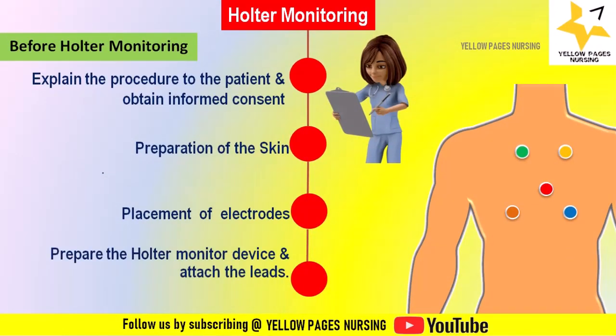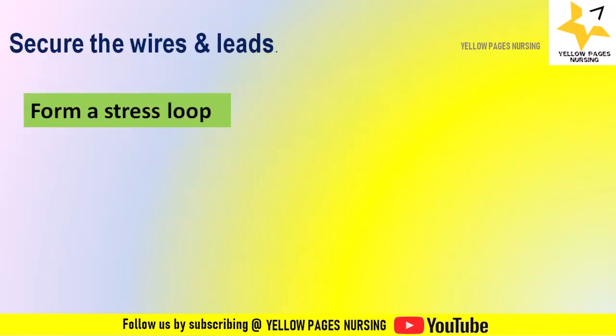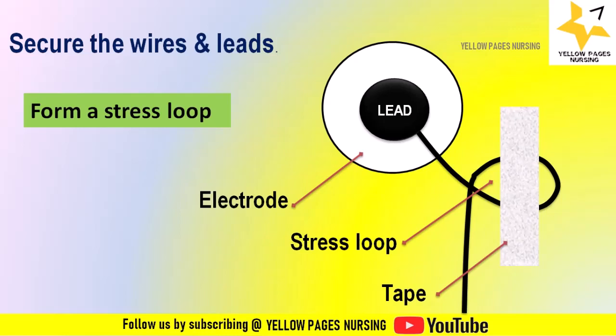Prepare the Holter monitor device, ensuring it is functional, has adequate battery life, and is ready to record data. Attach the leads to the electrodes and start it. Secure the wires and leads along the patient's body using medical tape or adhesive to prevent accidental disconnection. Form a stress loop with each electrode lead, tape the loop to the skin, and leave enough slack between the electrode and the stress loop.